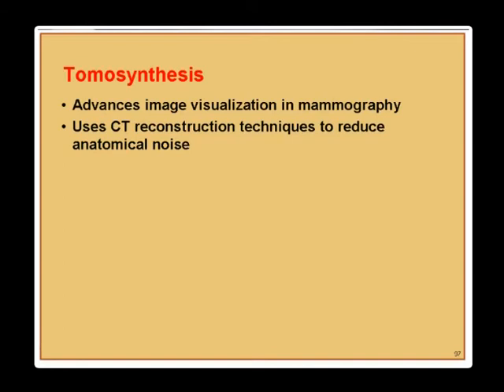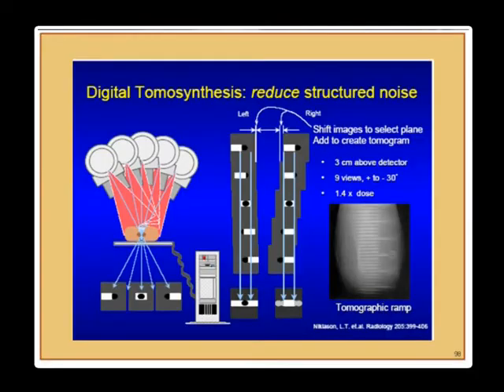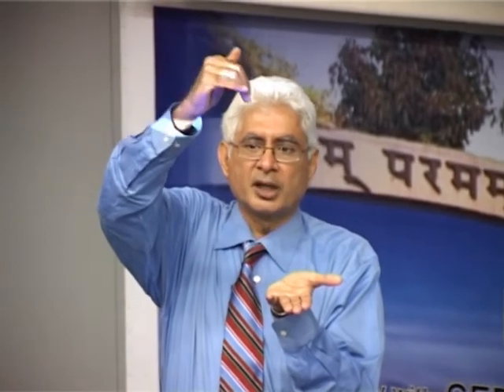Tomosynthesis is a recent advance from Mass General Hospital for image visualization in mammography. It uses CT reconstruction techniques to reduce anatomical noise. When X-rays pass through a compressed breast, overlapping anatomical layers obscure small microcalcifications or spiculated lesions — called anatomical noise. This was one reason why early digital systems showed little improvement over screen-film systems despite being more efficient.